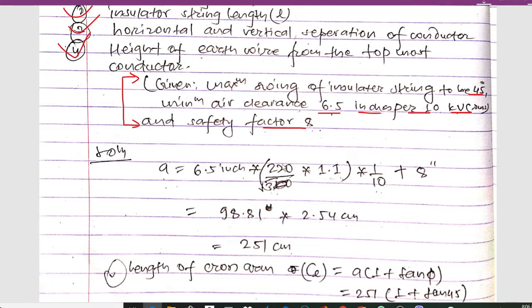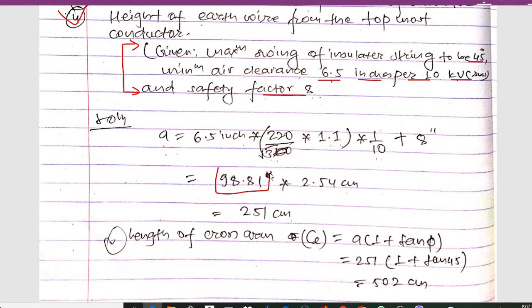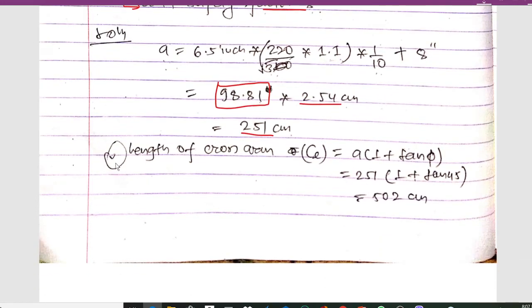The phase voltage is 220 divided by root 3, and for maximum system voltage we multiply by 1.1. With the minimum air clearance of 6.5 inches per 10 kV and safety factor of 8, the formula gives: A = 6.5 × (220/√3 × 1.1 / 10) × 8 = 98.81 inches. Multiplying by 2.54 to convert to centimeters gives 251 centimeters.